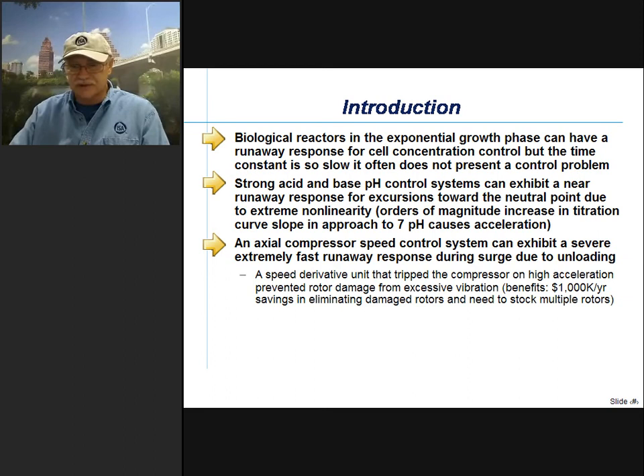I personally had experience with an axial compressor speed control system that can exhibit a severe, extremely fast runaway response during surge due to unloading. Within a second or two, we could get into trouble. So we installed a speed derivative unit that tripped the compressor on high acceleration, preventing rotor damage from excessive vibration. The benefits were over a million dollars a year in savings by eliminating damaged rotors and the need to stock multiple rotors. It was a very unique, very large axial compressor.